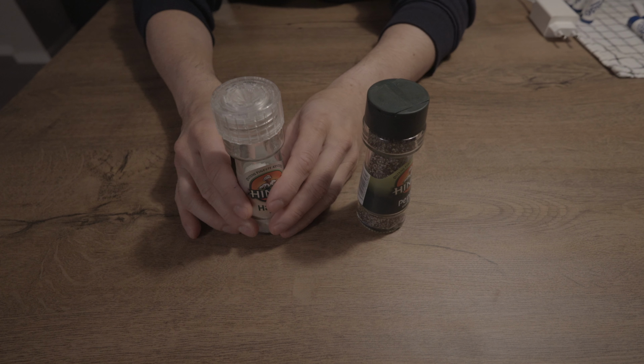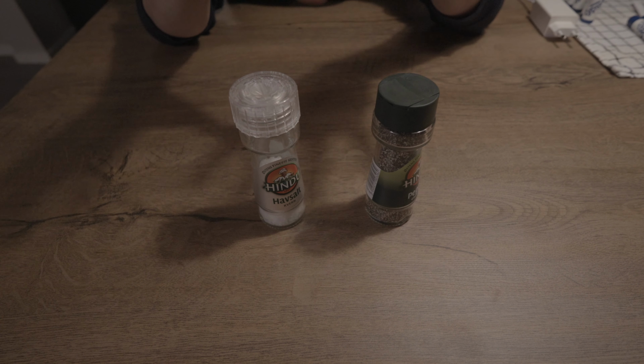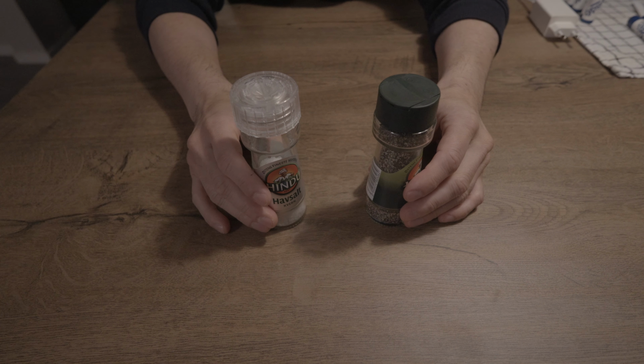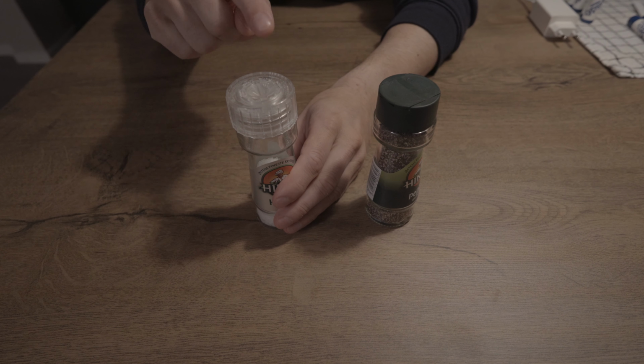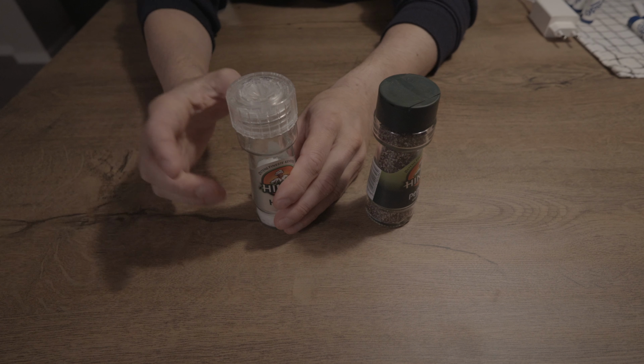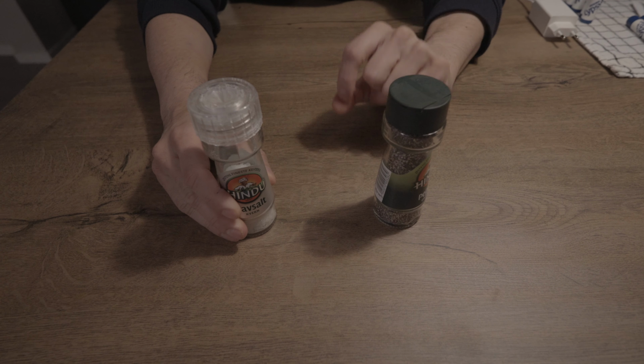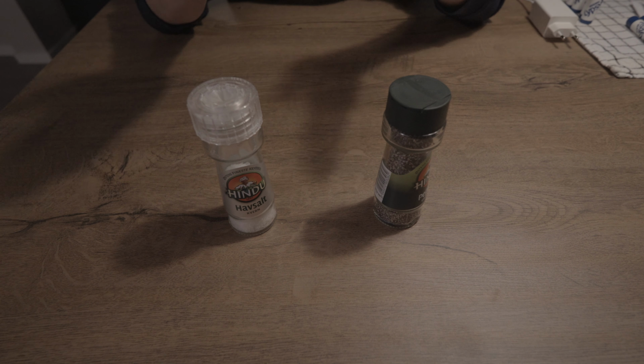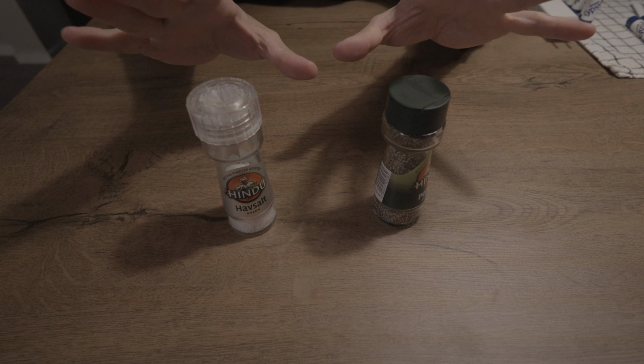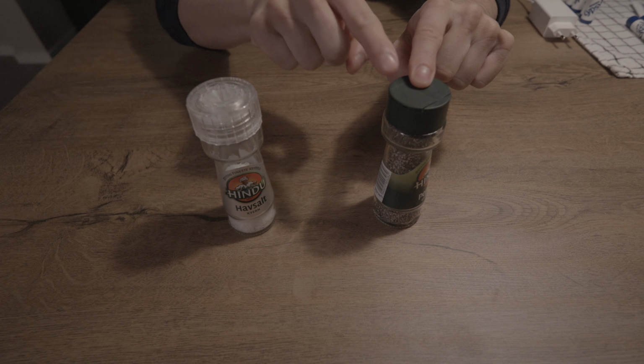And just say for the sake of argument that this is 200 kilowatts and this is 200 kilowatts. So 400 kilowatts at this charging site. But each of these cabinets can only peak at 200 kilowatts. It really doesn't matter if each of these cabinets has 4 times 50 kilowatt modules, 2 times 100, or 1 times 200. The fact that this is installed here with the power modules and this is installed here with the power modules means that you are reserving 200 kilowatts here and 200 kilowatts here from the power company that supplies power to this charging site. You cannot move power between these two.